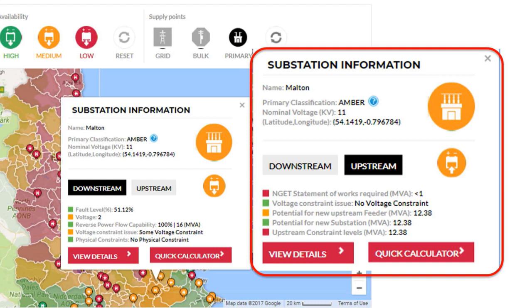The next one is talking about the actual 66 kV circuit and saying how much capacity there is in that circuit and the upstream network that we can accommodate. In this case, it's saying it's about 12.5 MVA, and it's also telling you that if you want to connect at 11 kV, you can only connect up to 12.5 MVA because the upstream network can't take any more.